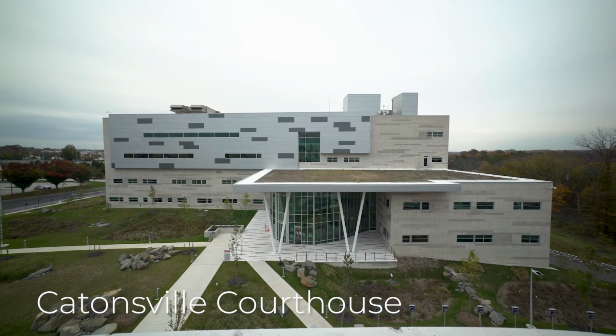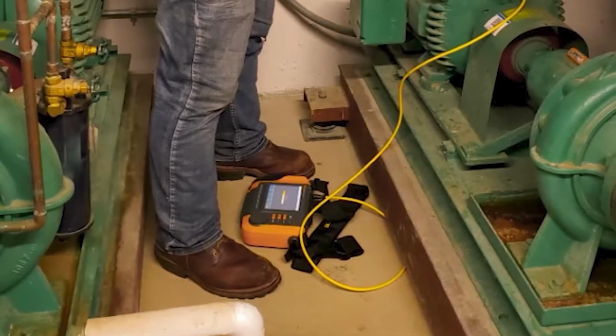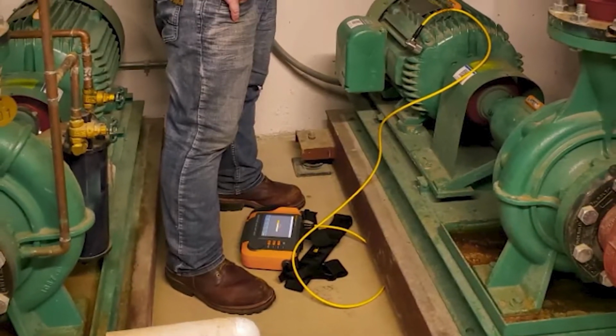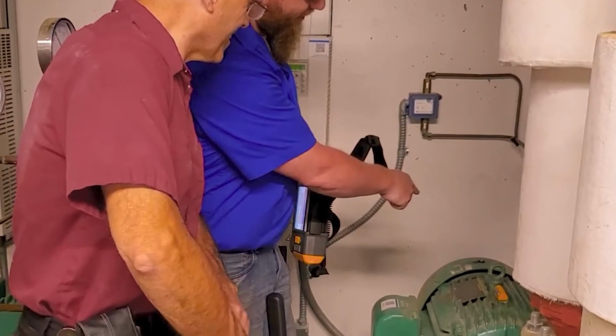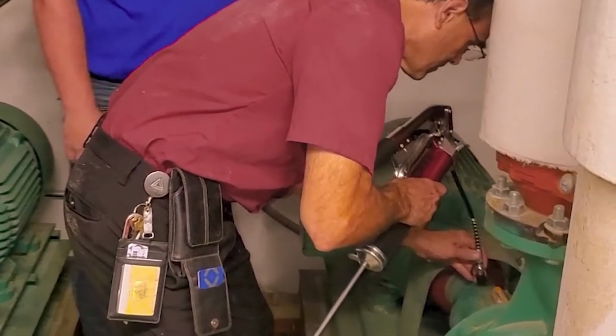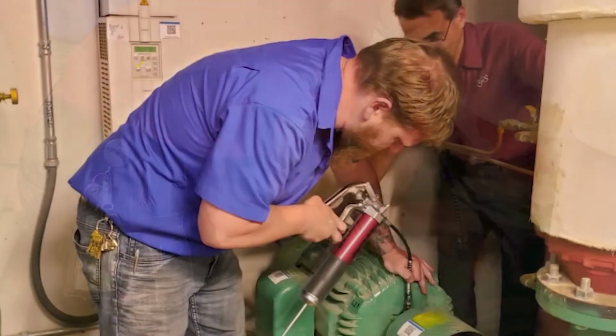At our Catonsville Courthouse, we had a sensor. We were able to look at the vibration from the sensor, and it said there's a problem, you need to address it immediately. We had staff go on site and look at the piece of equipment. They also took our predictive tools with them. They went and purchased a grease gun and some grease, which was roughly $60. Now, if we did not do this preventive maintenance at this time, it could have cost DGS and the state maybe $7,000 or more to fix this problem if it was left unattended.